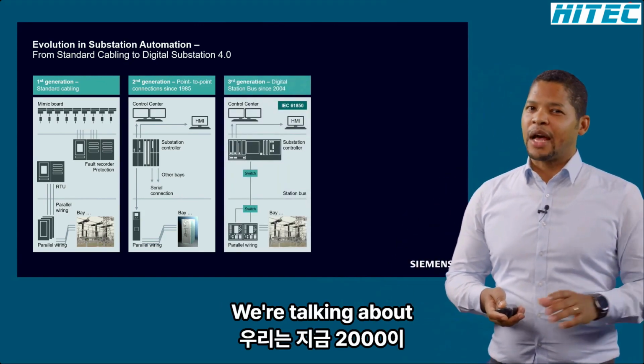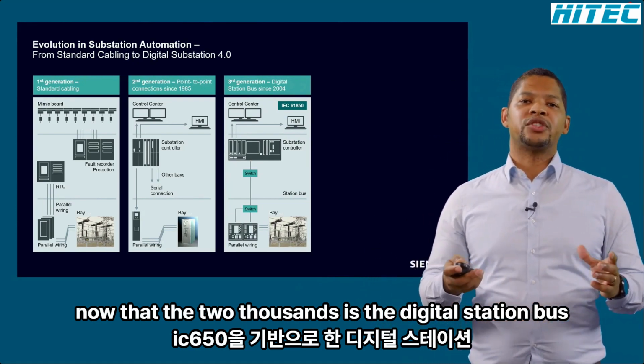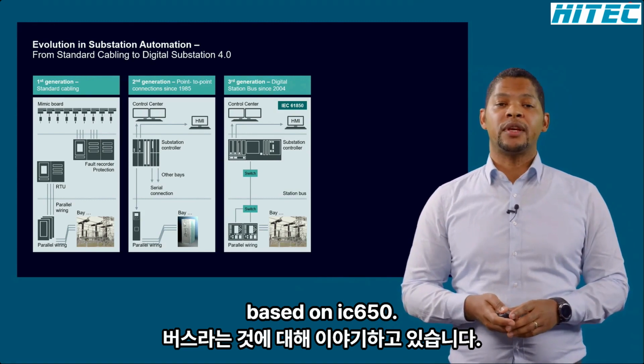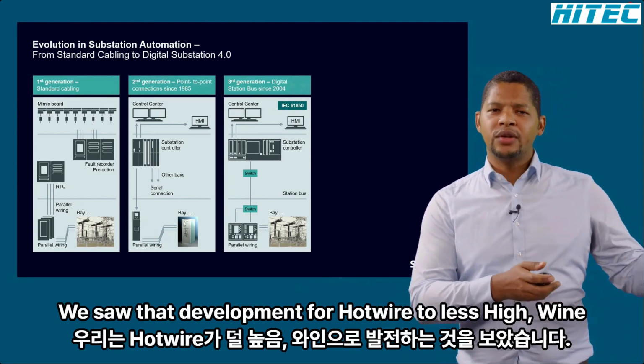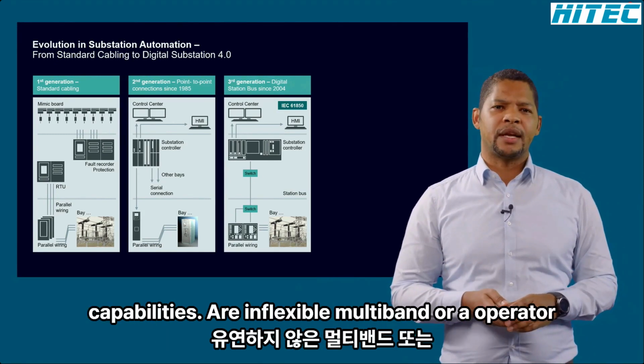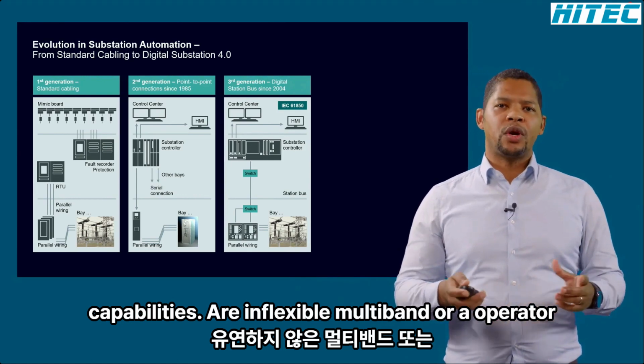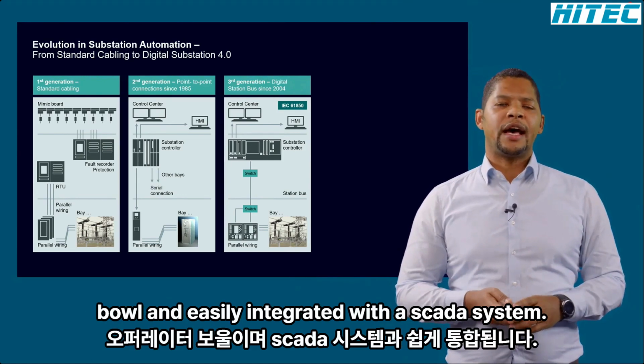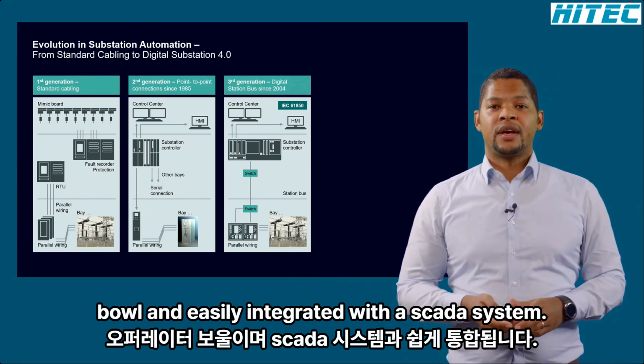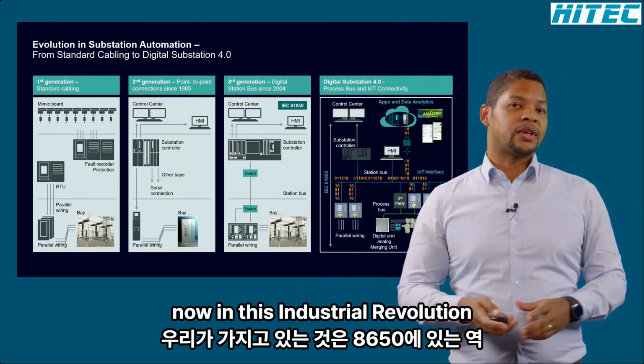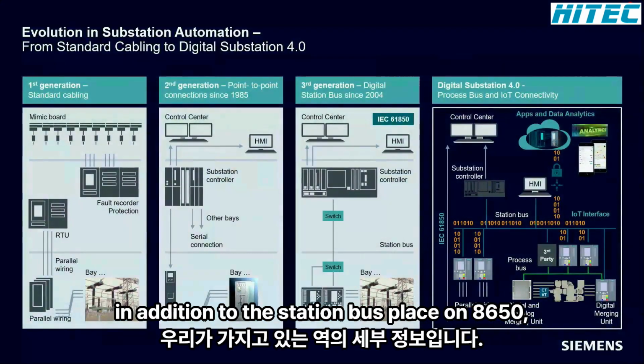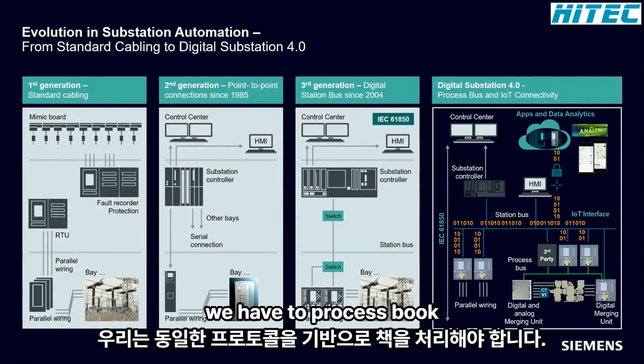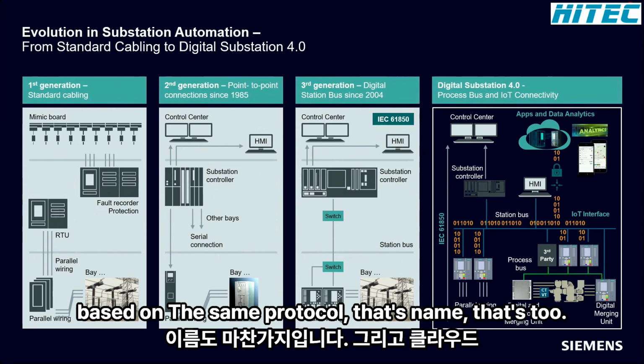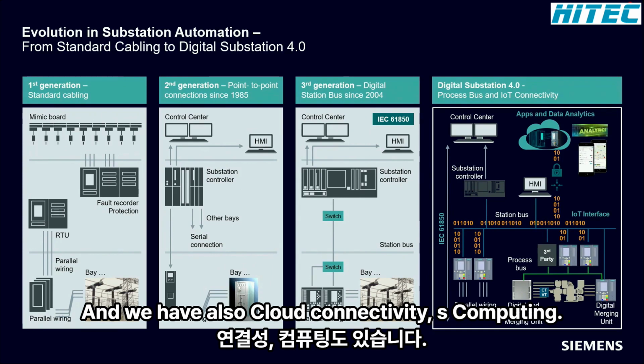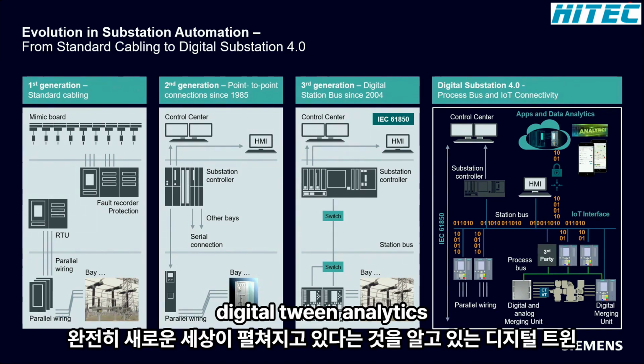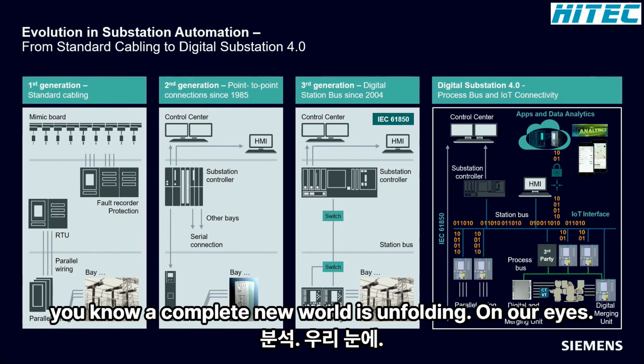The third generation, we're talking about the 2000s now, is the digital station bus. Based on IEC 61850, we saw that development from hardwired to less hardwired and more leverage on communication capabilities. Devices are fully modular and flexible, multi-vendor operable, and easily integrated with a SCADA system. What we have now in this industrial revolution is the digital substation, where we have, in addition to the station bus based on IEC 61850, the process bus based on the same protocol, part 9-2, and we also have cloud connectivity and edge computing. We have all those cloud applications, digital twin, analytics. A complete new world is unfolding before our eyes.